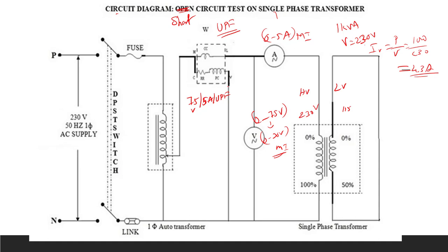These are the corresponding meter ratings according to the application. Using a single-phase autotransformer, fix the corresponding rated current. The power reading from the wattmeter will be the copper losses. The fuse rating will be 5 amps since 120 percent of 4.3 amps gives approximately 5 amps. This is the short circuit connecting methodology for the single-phase transformer.